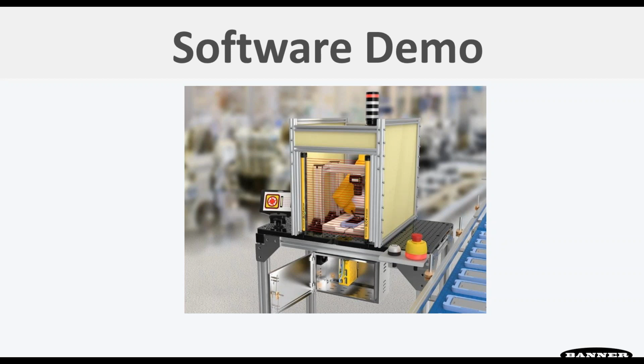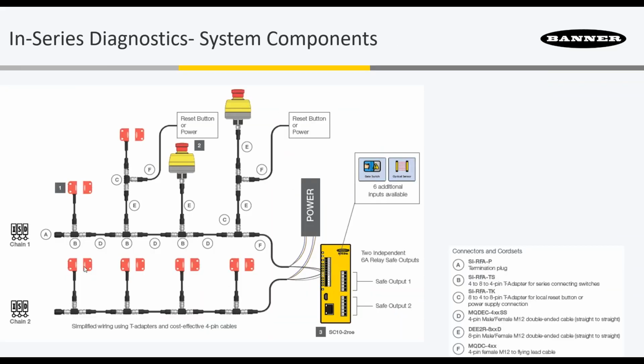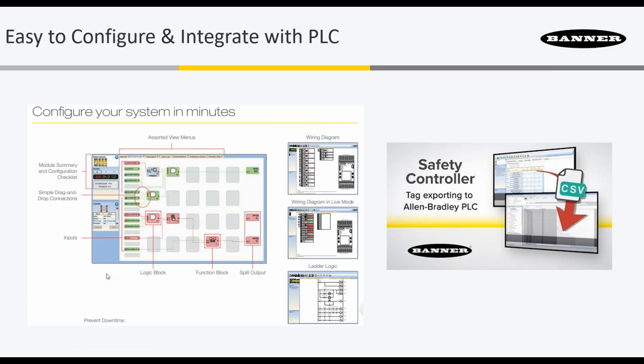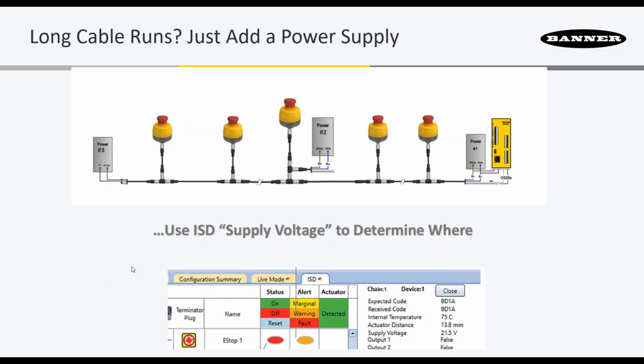So our diagnostic is a bit different. What we do is actually send a packet of information from each device. If I go back to this system, the way it works is this: it's actually a diagnostic protocol that rides on the OSSD lines, and it's a patented, unique system - there's nothing else like it on the market. What it does is take all the information from the sensor and send it to the next one. That one adds its information to that, and so on. So it's a linear daisy chain, and all that information from each device is sent into the SC10. It does some work to make it really easy to read in a PLC and sends that out. So there's a lot more data that you get with our system, so we can prevent downtime. We can alert you when a door's starting to sag. We can tell you the voltage level of the system, and it's not just a matter of saying what device is tripped and where.